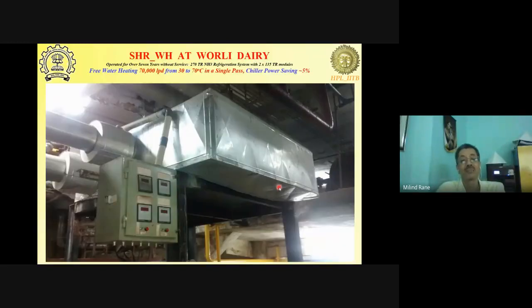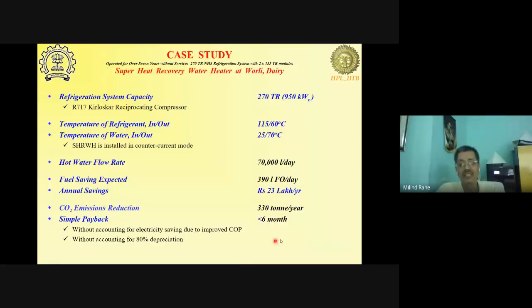This is another example of superheat recovery where 70,000 liters of hot water is produced in a single pass from 30 to 70 degrees centigrade. This was recovered from a 270-ton ammonia refrigeration system. There were 2 modules of 135 tons, and the chiller power saving was 5%, and of course all the hot water was free. Again, the payback we had promised was 6 months, and we got less than 6 months. The annual saving was 23 lakh rupees, and the cost of the installed system was 10 lakh rupees. The emission saving per year was 330 tons.